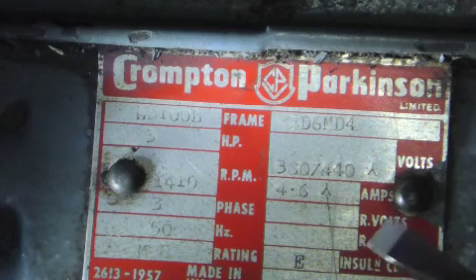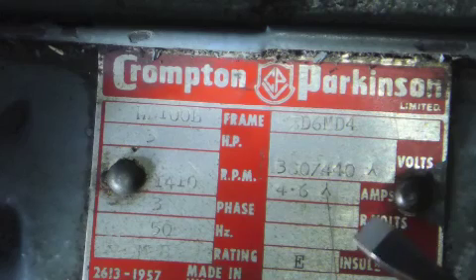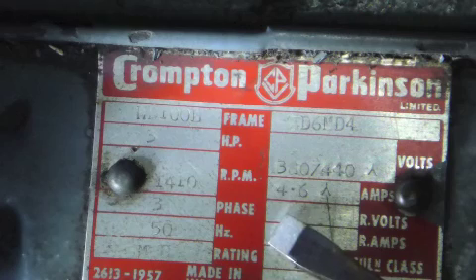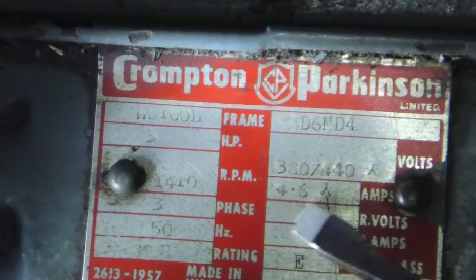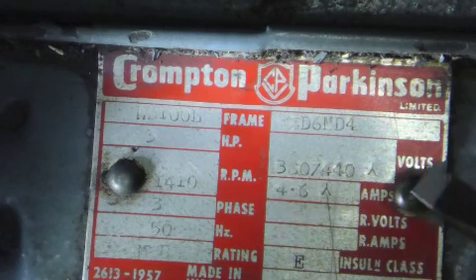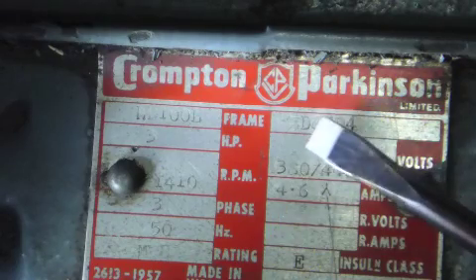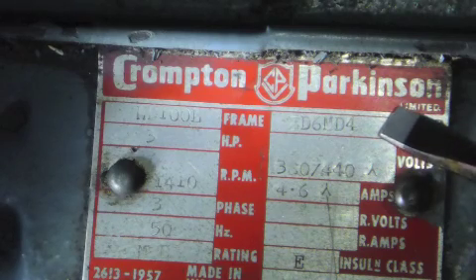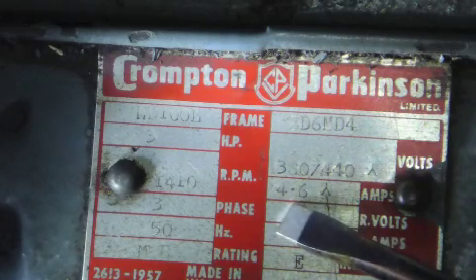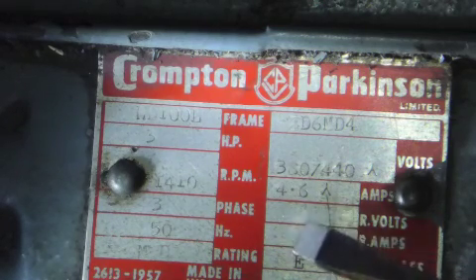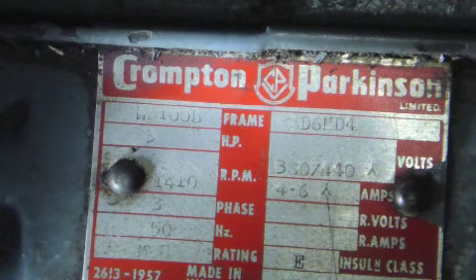If it's a dual voltage motor you can look in the amps field and you'll see two different sets of current readings. This one has one set of current reading it says 4.6 amps. If it was a dual voltage motor you'd be looking at something that says 240 to 415 and the amps corresponding to 415 would be approximately half of the amps that correspond to 240.